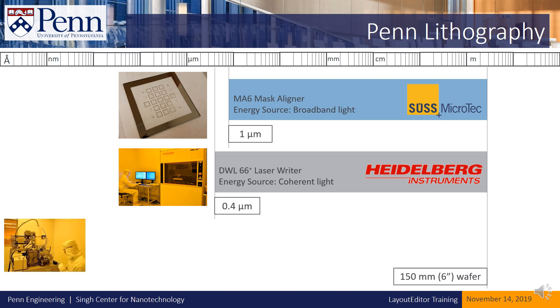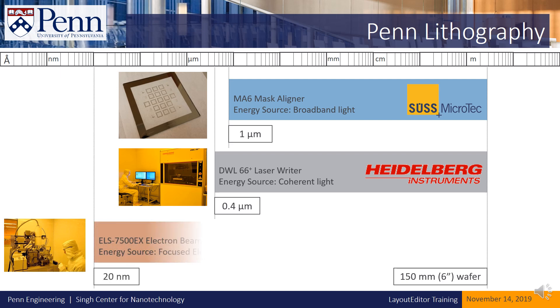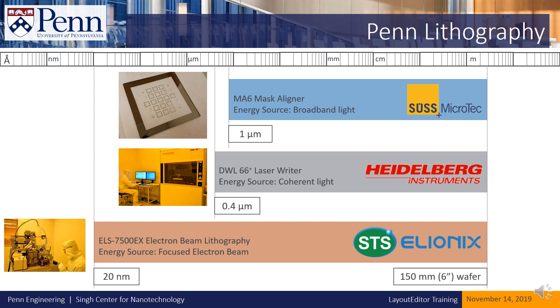If you need to print features smaller than 400 nanometers, you should consider using the Elionix ELS7500EX Electron Beam Writer. This tool can write features down to around 20 nanometers, but the write times for the Elionix are much longer than they are for the Heidelberg or the MA6.